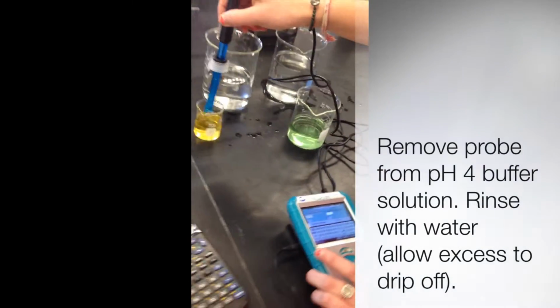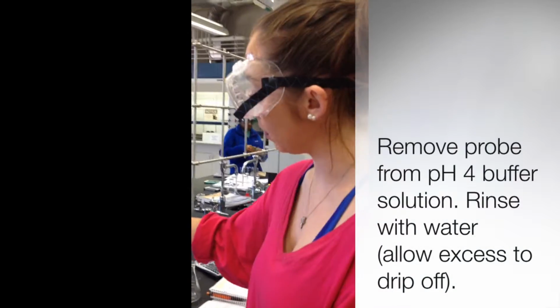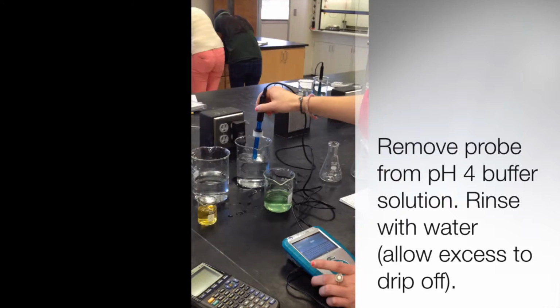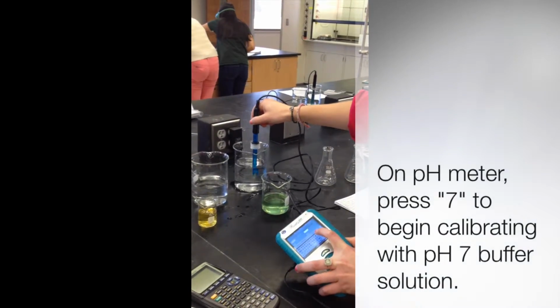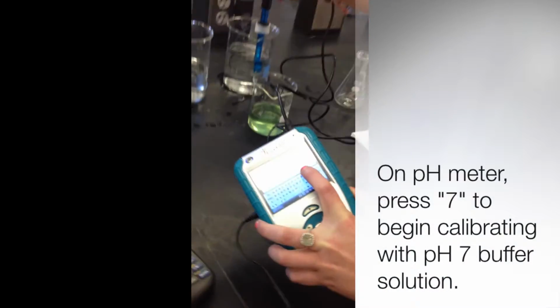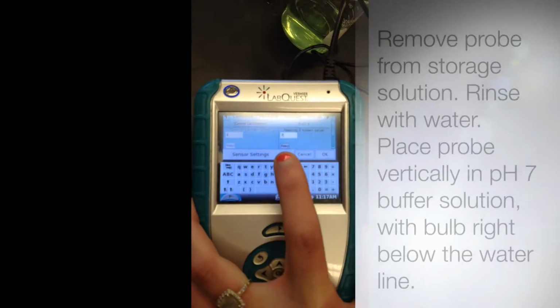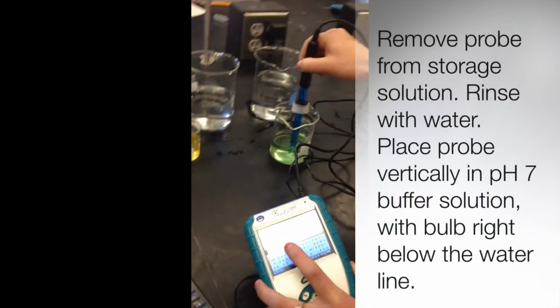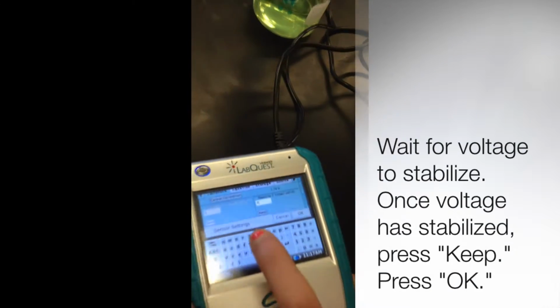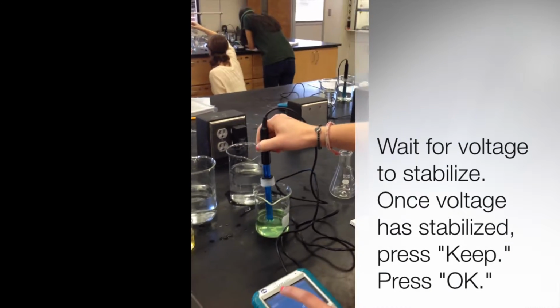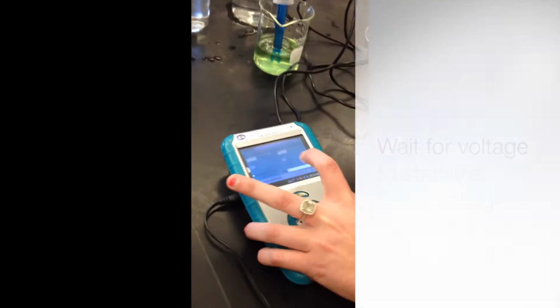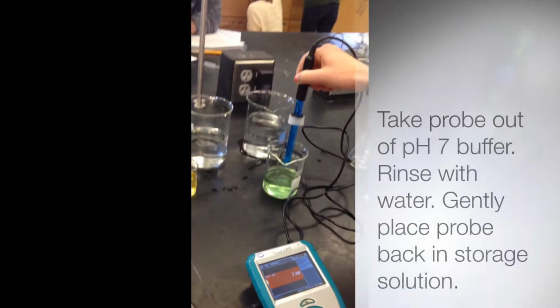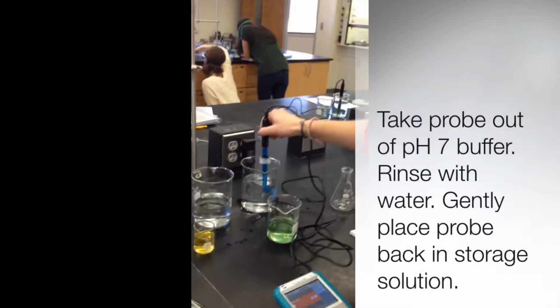And then I'm going to take the probe out of the pH 4 buffer solution. I'm going to rinse it again in the H2O. And I'm going to go ahead and press 7 for the new calibration. And now I'm going to place it in the pH 7 buffer. And we're waiting again for the voltage to stabilize. It looks like it's stabilized at around 1.74, and we're going to press keep. And then we're going to press OK. I'm going to take it out of the pH 7 buffer, rinse it again in water, and then put it back in the storage.